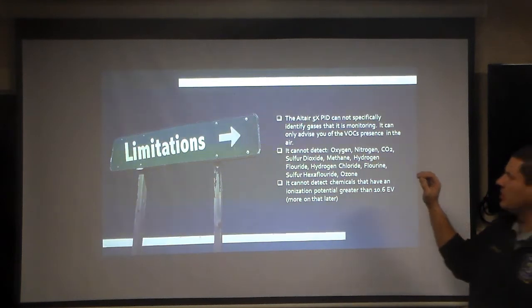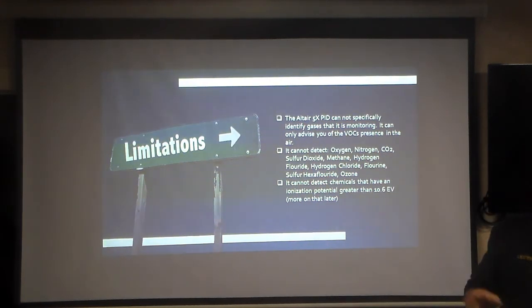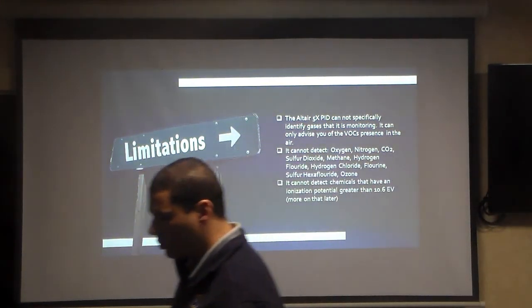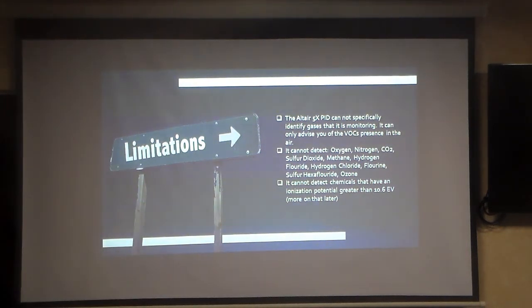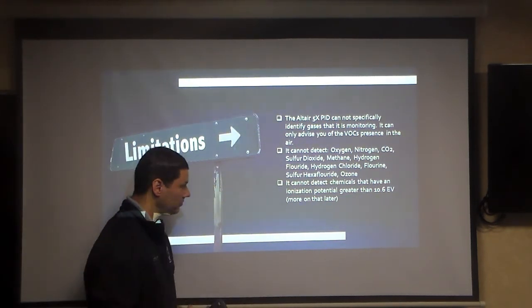One of the biggest limitations is that this meter, once it's turned on and once it's doing its thing, will not tell you what it's reading. It does not know that. So you can't take this into a room with an unknown odor and expect it to tell you specifically what's in there, which is okay. We don't care, but just don't think this is going to tell you what gas is in there. It won't do that.